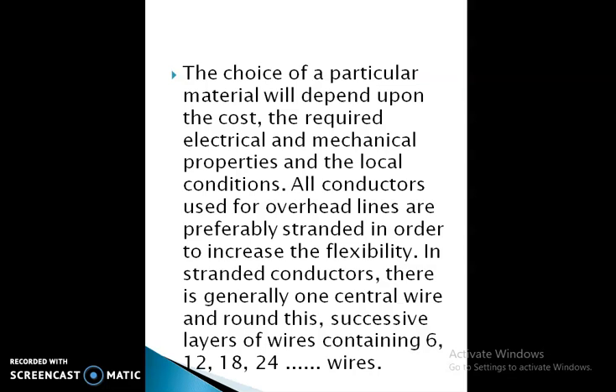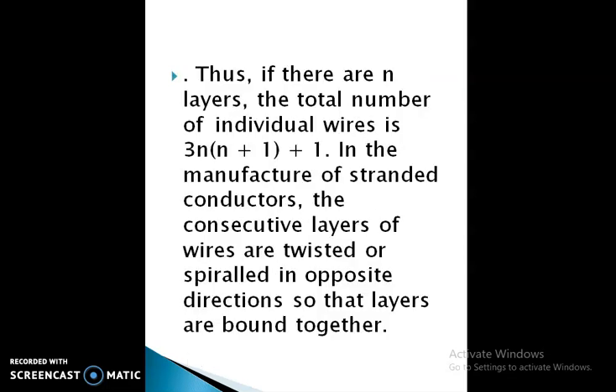All conductors used for overhead lines are preferably stranded in order to increase the flexibility. In stranded conductors there is generally one central wire, and around this successive layers of wire containing six, twelve, eighteen, twenty-four wires. If there are n layers, the total number of individual wires is 3n(n+1) + 1. In the manufacture of stranded conductors, the consecutive layers of wire are twisted or spiral in opposite directions so that the layers are bound together.